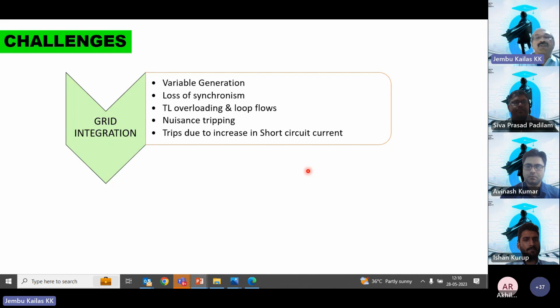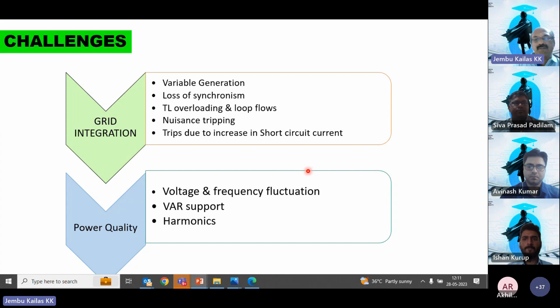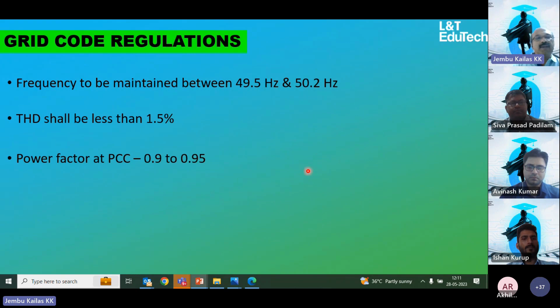Power quality issues like voltage and frequency fluctuation, VAR support are there. Even though today, to some extent, inverters are able to supply VAR to the system, this is still a question, and harmonics are still a question. As per grid code, you have to maintain frequency within a bandwidth, total harmonic distortion should be less than a specified limit, along with power factor requirements.